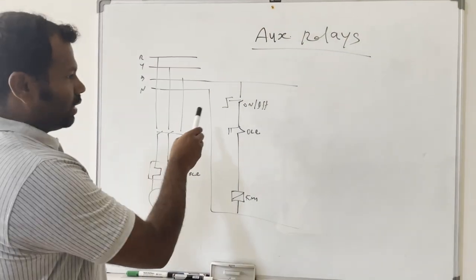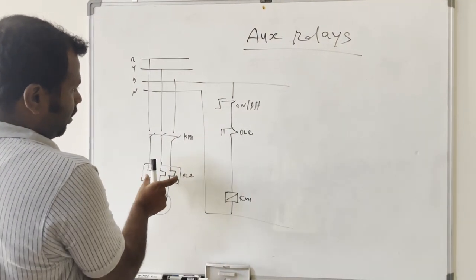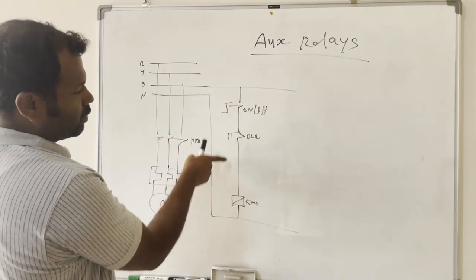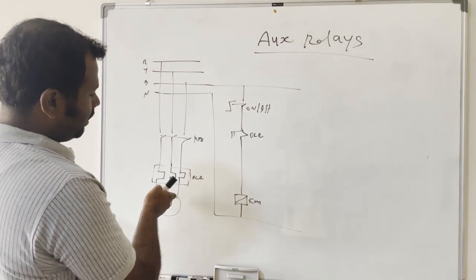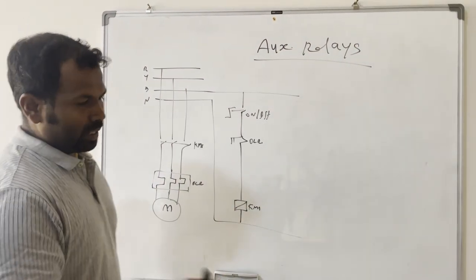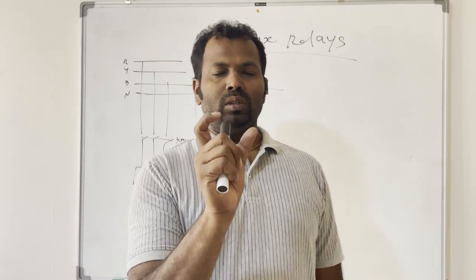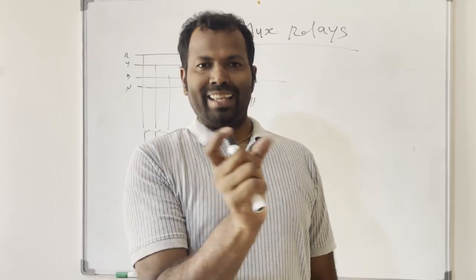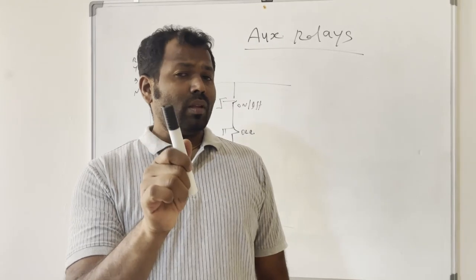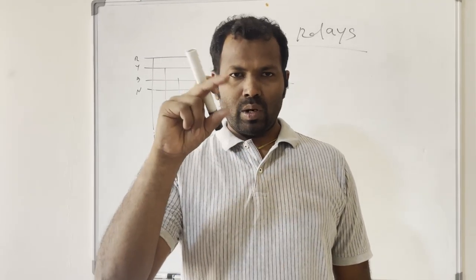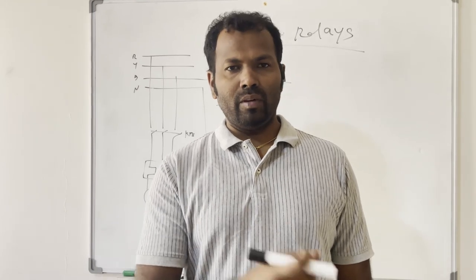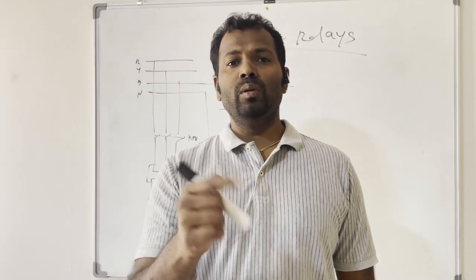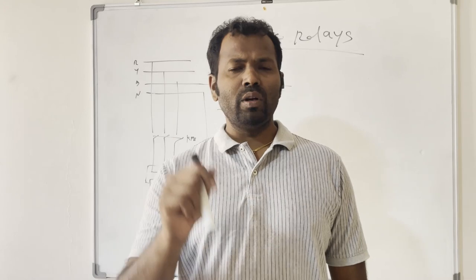This is a normal DOL starter. You can see one contactor, an overload relay, and a control circuit with an on/off switch. Once you switch on, the contactor energizes, supply feeds to the motor and the motor turns. Now, you want to give a volt-free contact to your remote area like PLC or SCADA showing that your motor is running. However, not all contactors are available with auxiliary NO/NC contacts.